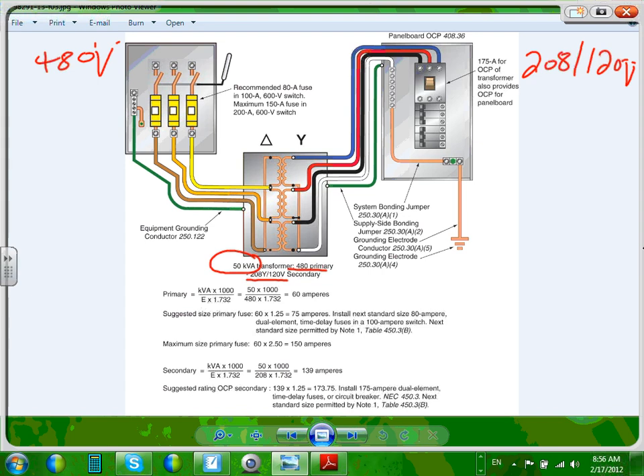The first thing to size, we need to size these cables, guys, here, and we need to size the fuses, and we need to size the circuit breaker on this side, right? That's what they hire us to do. To size the primary, can you guys see how the example, to size the primary, find the full load current on the primary side, piece of cake. Take the kVA divided by the voltage and 1.73, gets you 60. So that's the primary.